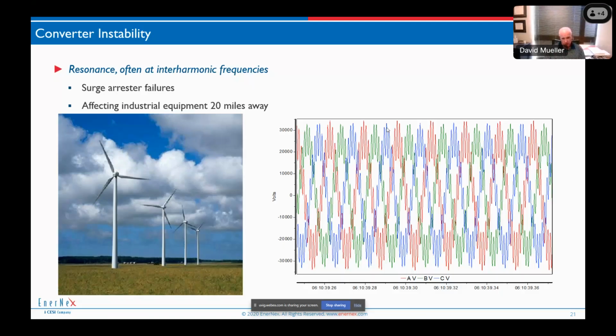In one place, transformers on an industrial plant 20 miles away were making noises, singing these higher frequency harmonics. You can see each sine wave here shows what looks to be harmonics. But actually, if you look at these waveforms closely, you'll see that they don't actually repeat themselves every cycle. If you look at the peaks, they differ from cycle to cycle. And what that tells me is that the voltage here is actually an interharmonic. It's in between harmonics. And we can see as high as 40% distortion in these cases.